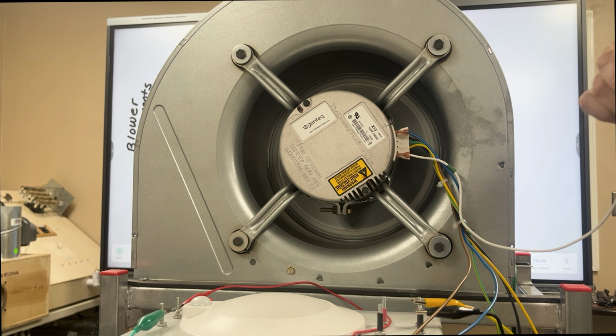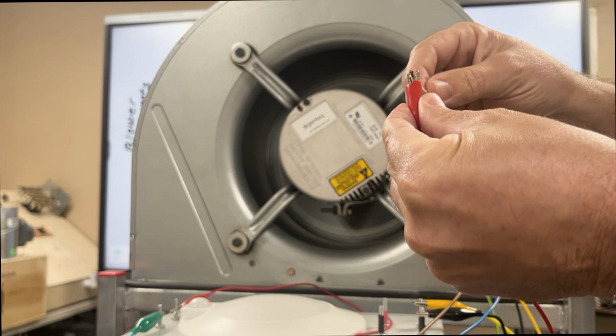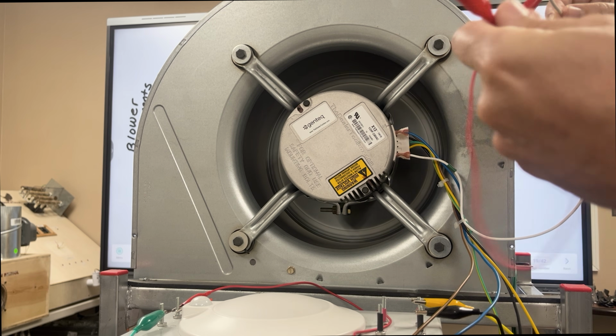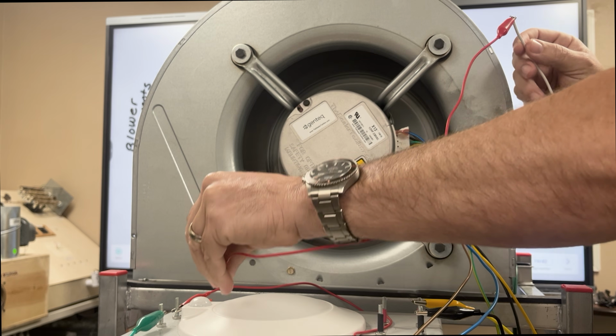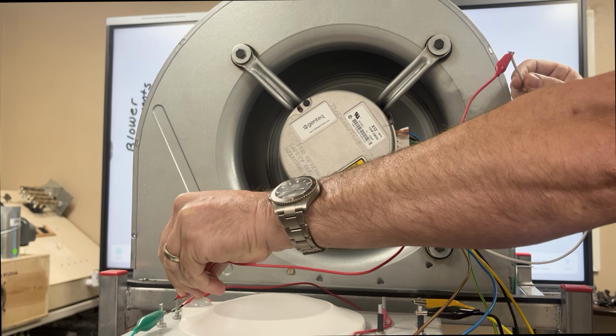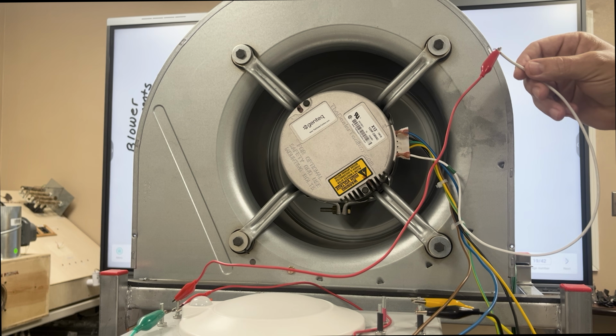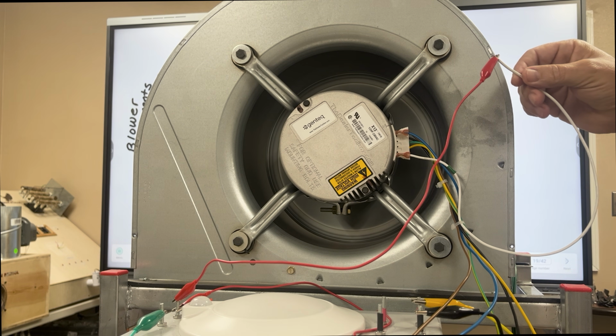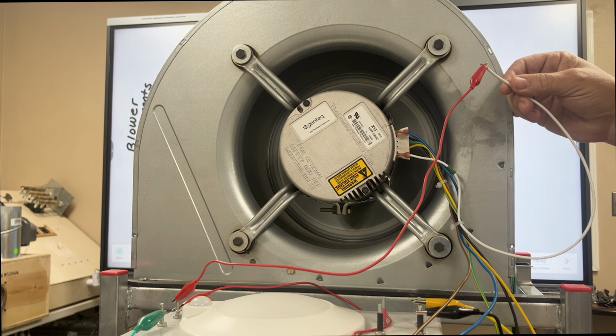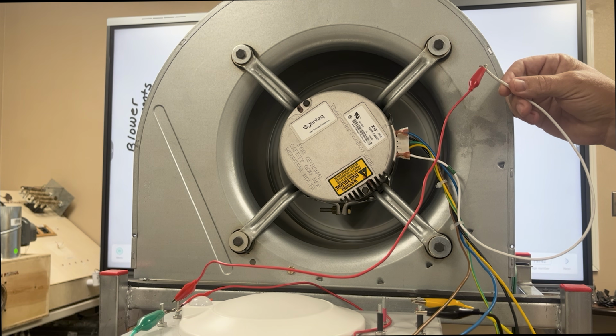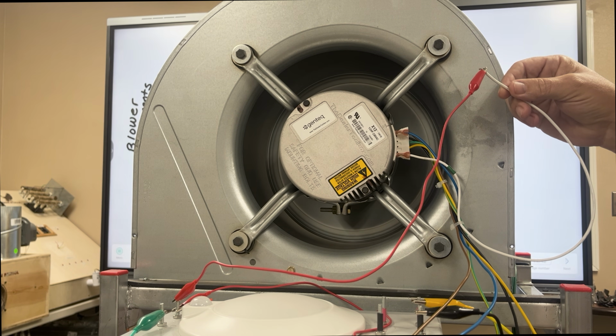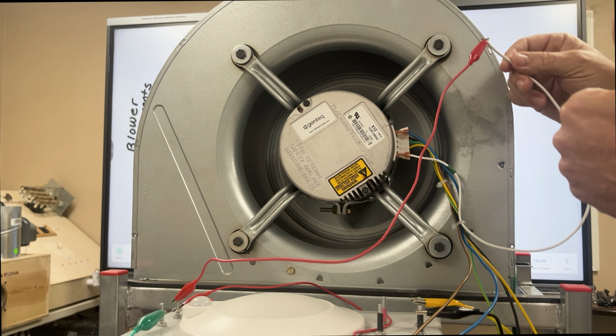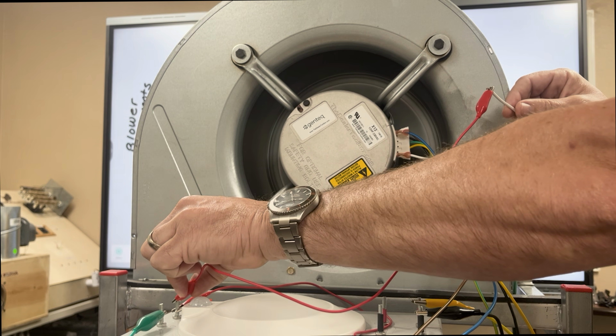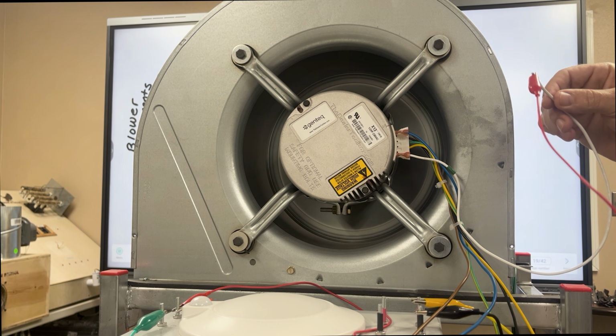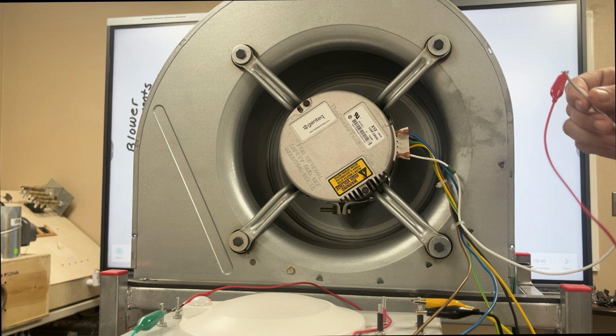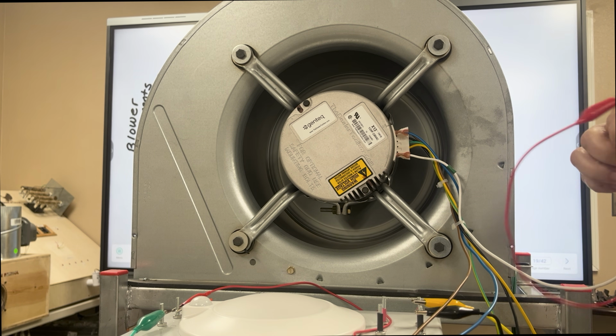And to show you here, I'm going to connect 5 to my alligator clip and take the other end of my alligator clip and connect it over here to 24 volts. And you'll hear the motor pick up in speed. All right. And we are now running speed tap 5 only. It is ignoring the call for 1, but if we were to remove power on 5, the motor will reduce its speed to the last call, which is terminal 1.